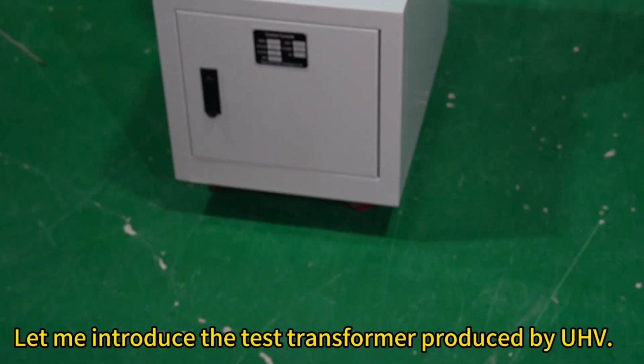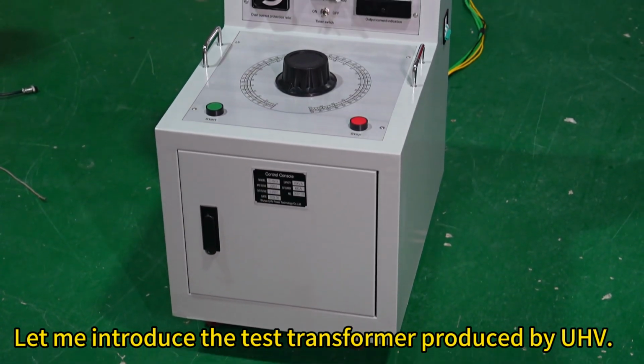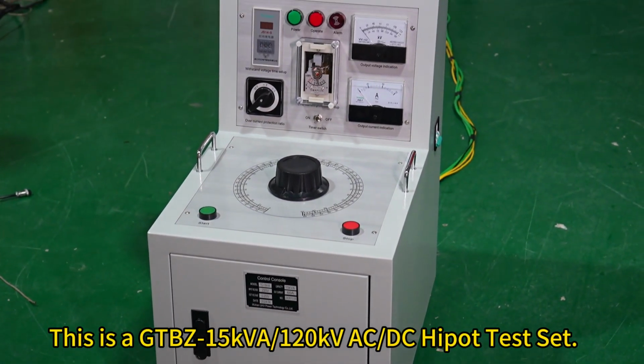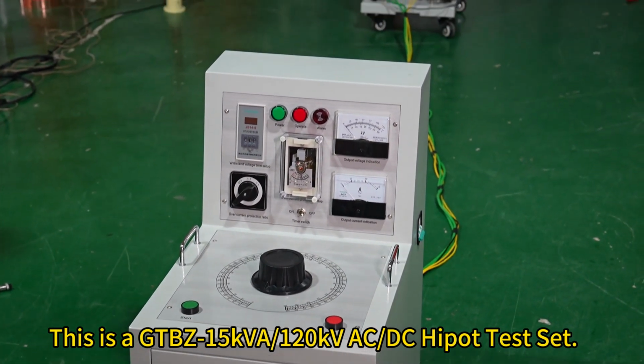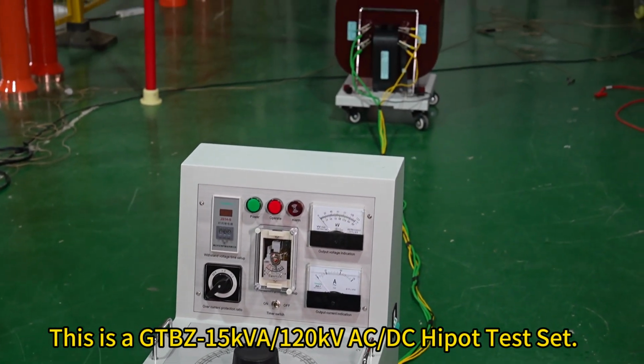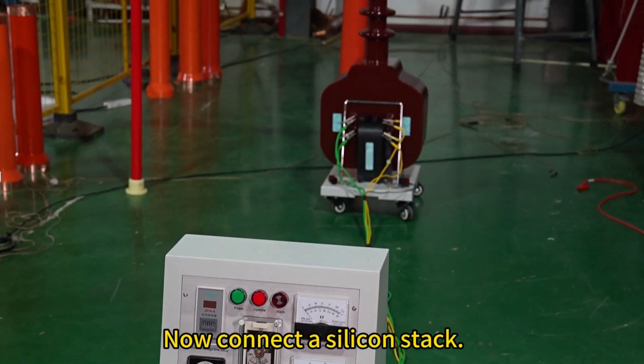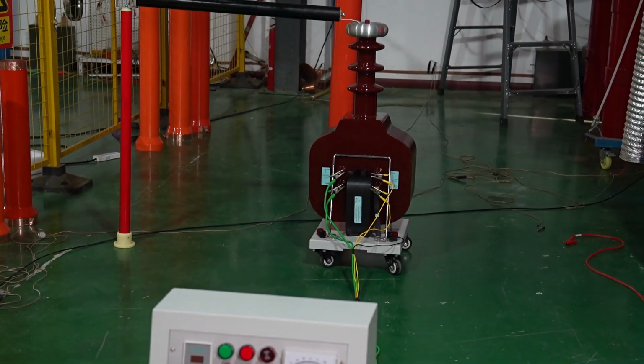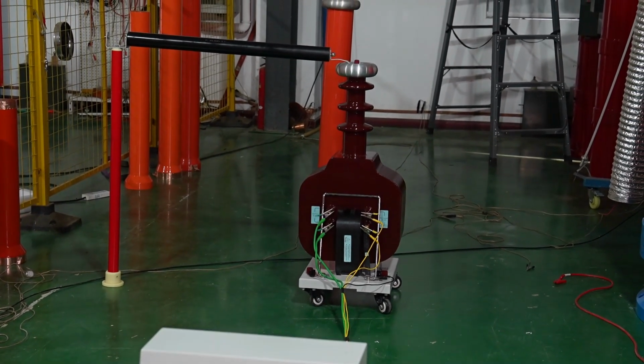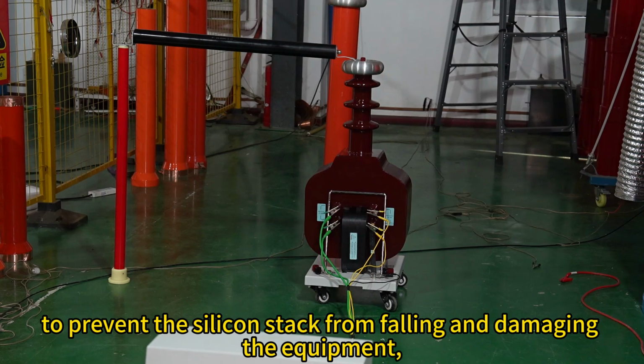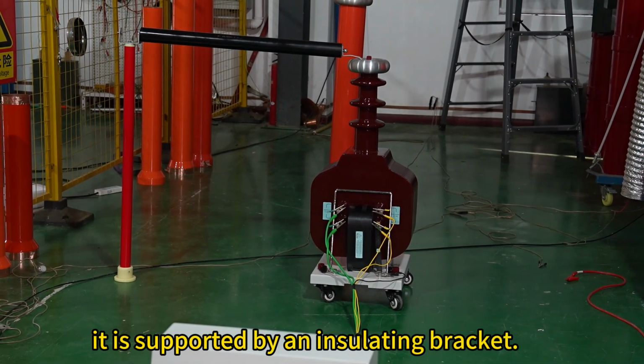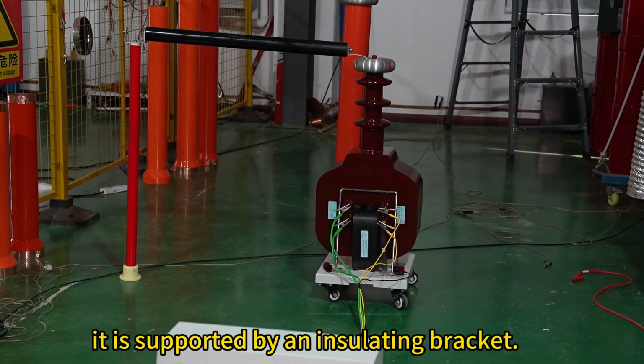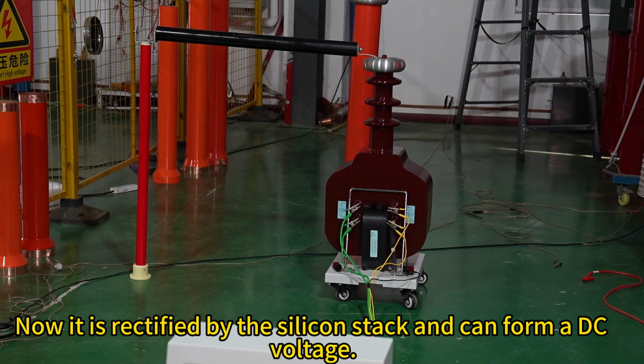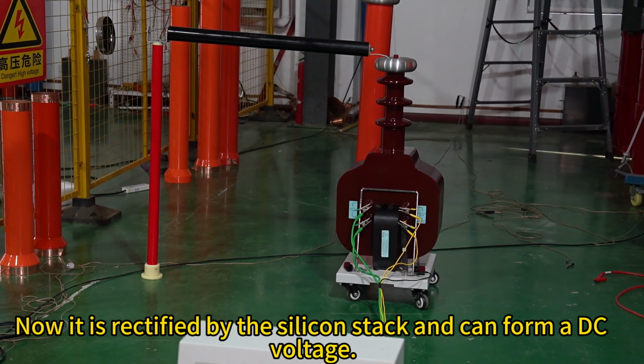Let me introduce the test transformer produced by UHV. This is a GTBZ-15kVA/120 kV AC/DC Hipot test set. Now connect a silicon stack. Since the silicon stack is long, to prevent it from falling and damaging the equipment, it is supported by an insulating bracket. Now it is rectified by the silicon stack and can form a DC voltage.